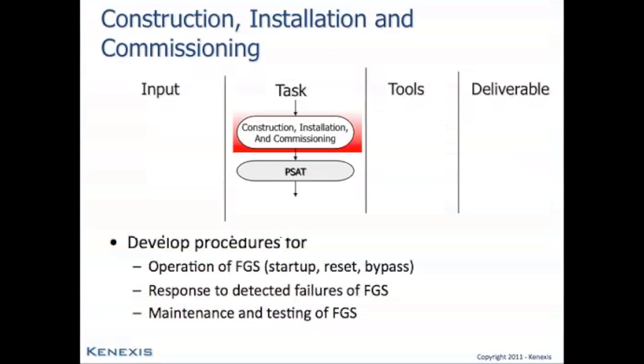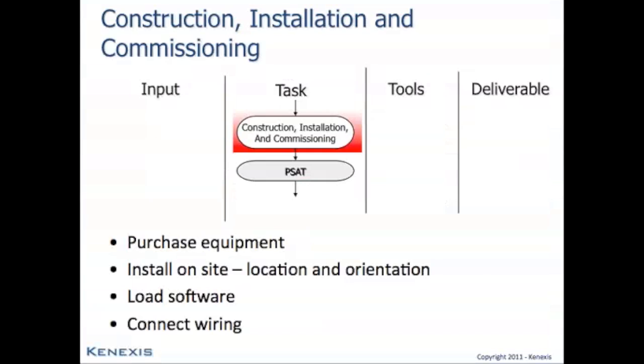After procedure development and after the detailed design has been performed, the system is built and it is installed and commissioned on site. This task, again, is very similar to traditional fire and gas system design and instrumentation and control system design in general. This task involves the purchasing of the equipment, the construction of the cabinets and assembly of the equipment into cabinets, then the installation of the cabinets and the field equipment and all the interconnecting wiring on site.